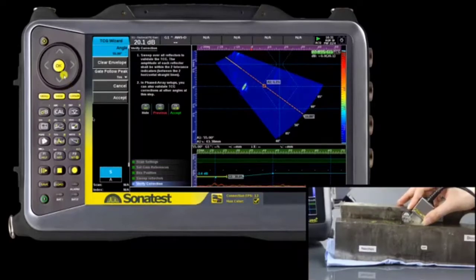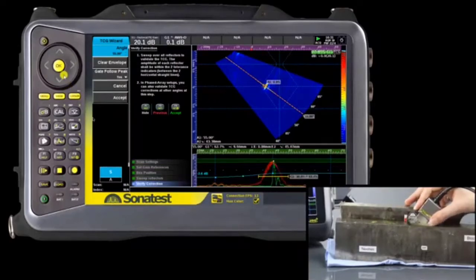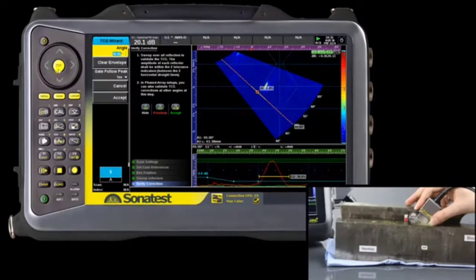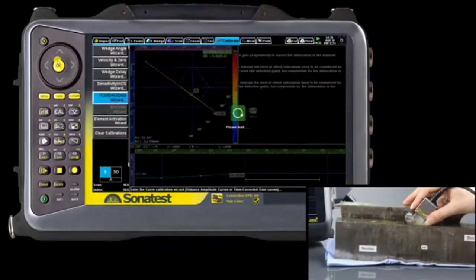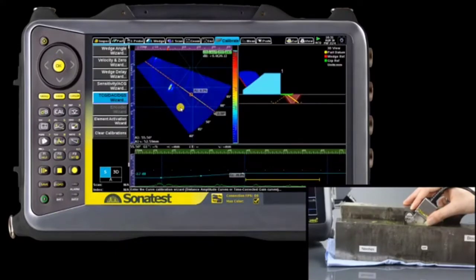The last step is to validate the obtained curve. Every reflector on every angle should fall within the tolerance of 80% signal response. We should also see that every angle has a distinct TCG curve. Once completed, all the calibration markers will be green and the signal response for a given reflector would be the same regardless of its depth, distance from the wedge or the angle beam orientation.